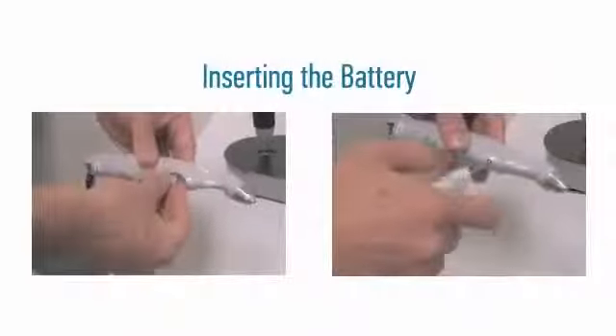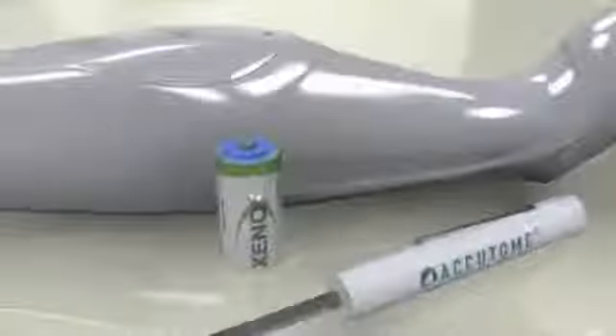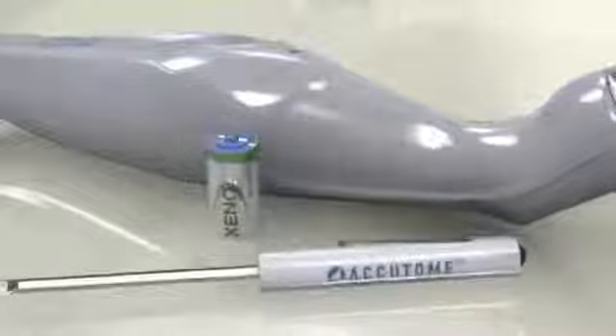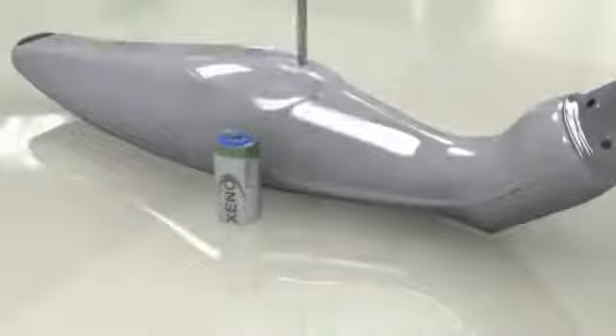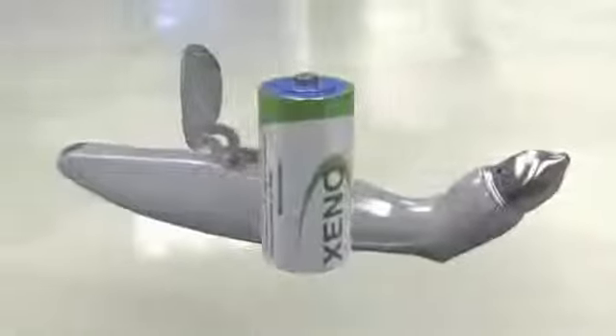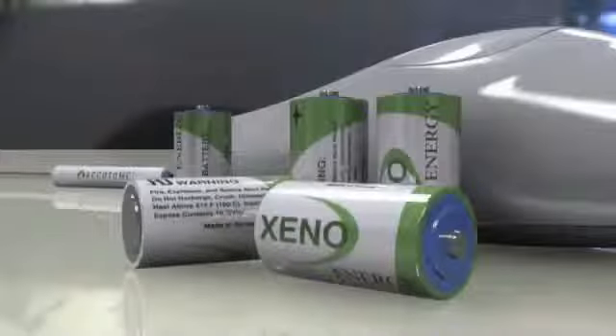Inserting the battery. When you first unpack your AccuPen, the 3.6-volt lithium battery must be placed inside the unit. Take the screwdriver to open the casing and place the battery inside of the unit. Use the screwdriver to tighten the compartment shut. Be sure not to over-tighten the screw. Batteries typically last 15,000 measurements or 1 year and can be purchased directly from Accutome.